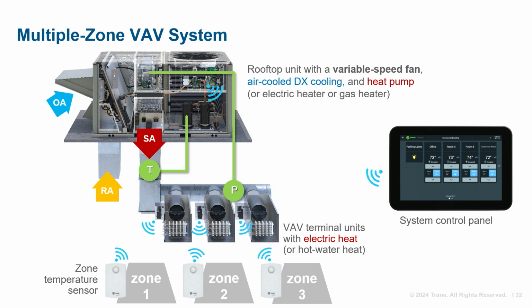Also, during normal operation in cold climates, the recirculated outdoor air mixture might need some heat to ensure cold air is not delivered down the duct to the VAV boxes. So the rooftop will use SCR electric or modulating gas heat to provide supply air tempering, which heats the supply air to a set point, perhaps 60 degrees Fahrenheit. The rooftop does not need an air bypass because the system relies primarily on the VAV boxes to modulate airflow and provide heat.